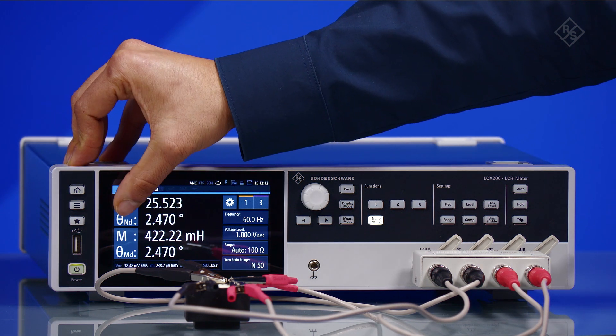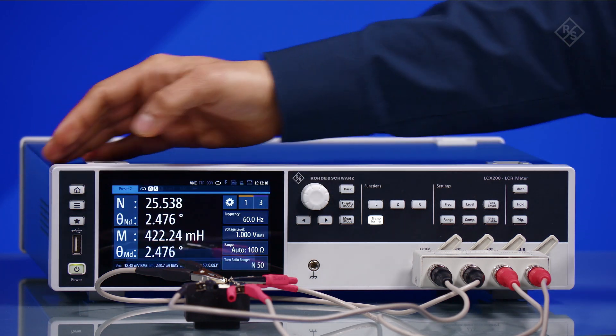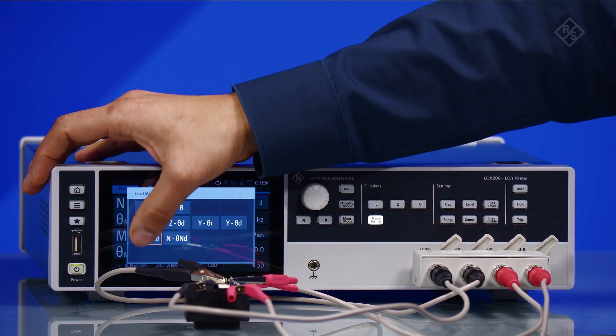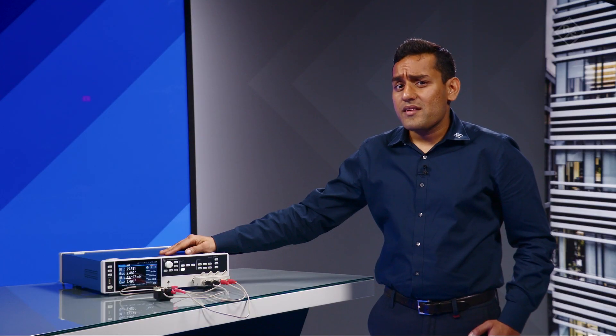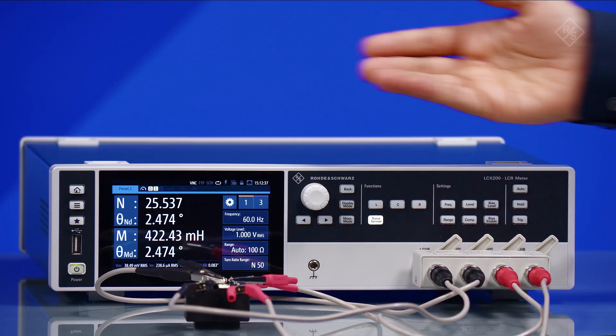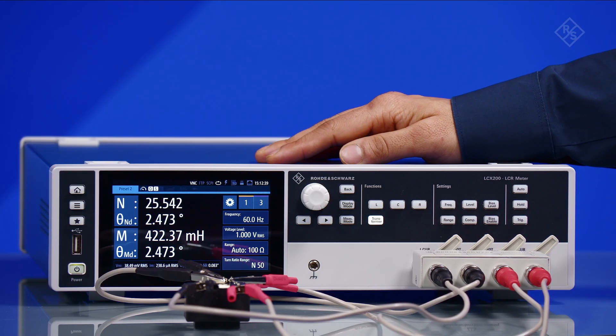The device measures the required primary and secondary parameters. And now this is really a very cool feature in our LCX 200. You need not do any calculations for mutual inductance and turns ratio. The values are displayed directly on the LCX screen.